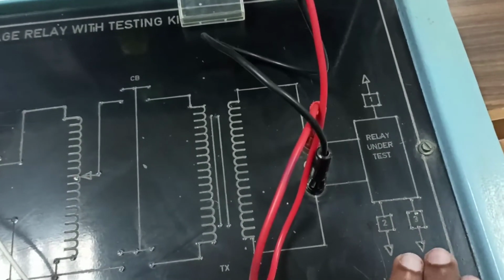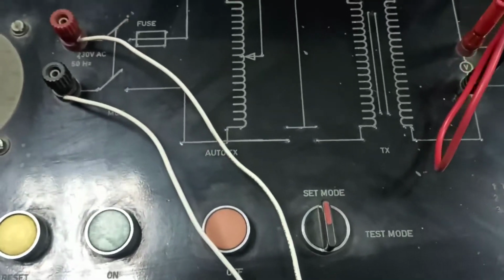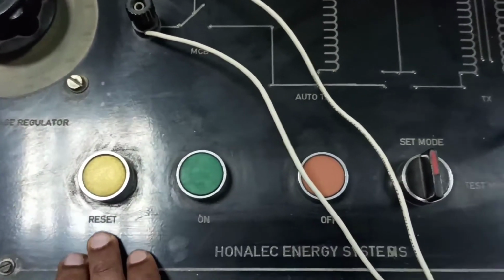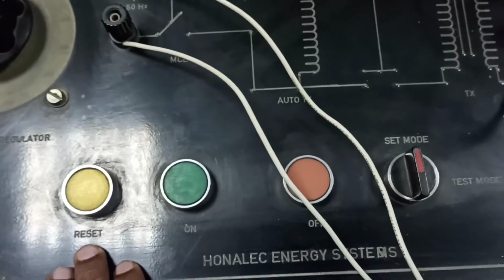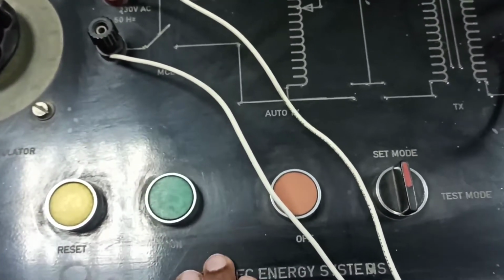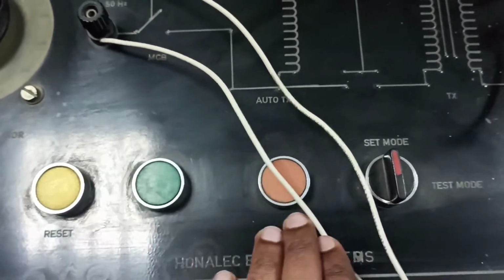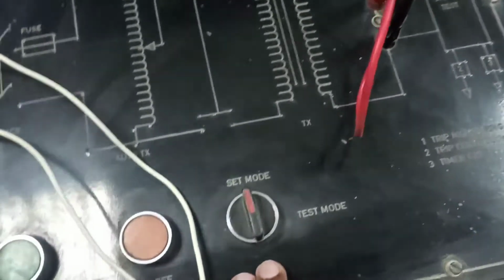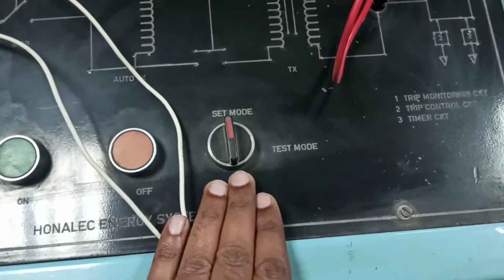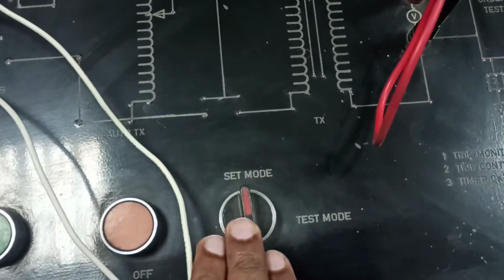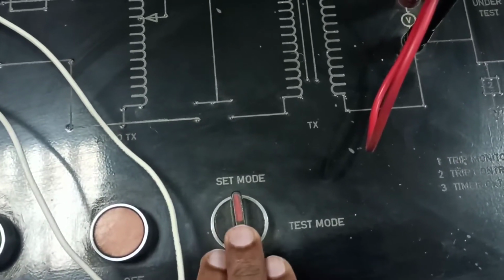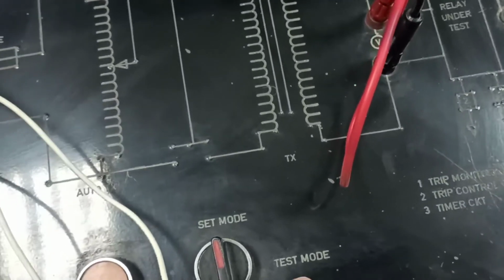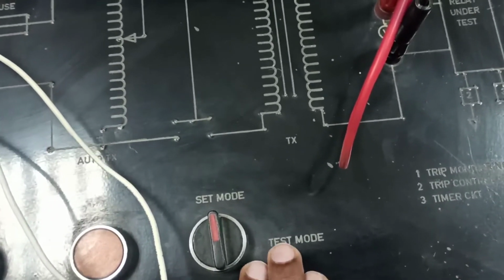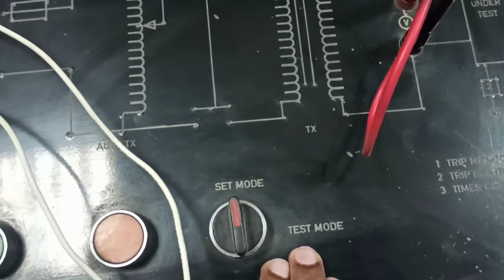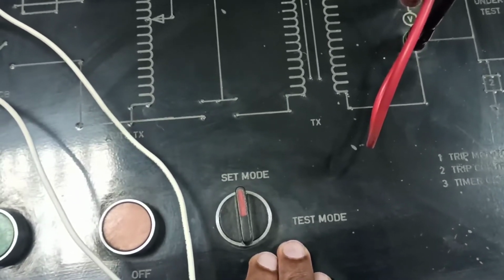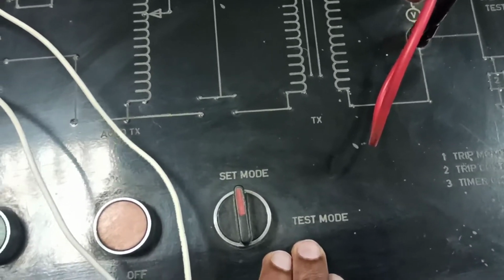Okay, so we are going to test the relay, and these are the buttons. This is to reset any previous programming of the relay. This is for turning on the kit, and this is for turning off the kit. This is set mode and test mode. When we are going to set the timer for the relay, we keep it on set mode, and when we are going to test the relay, we keep it on test mode. So while plotting the characteristics, we keep it on test mode.